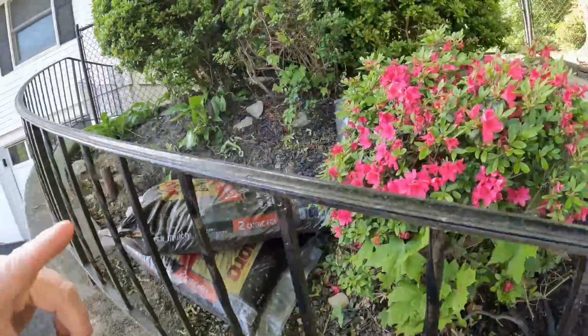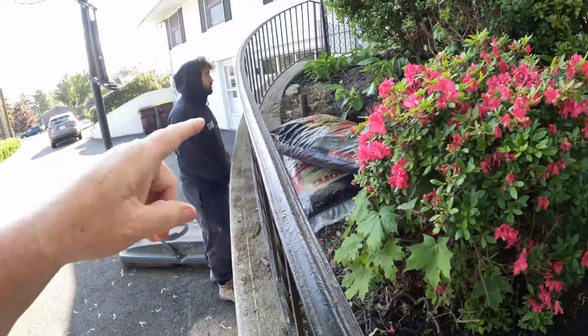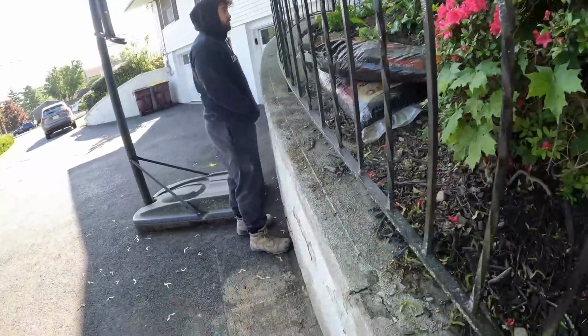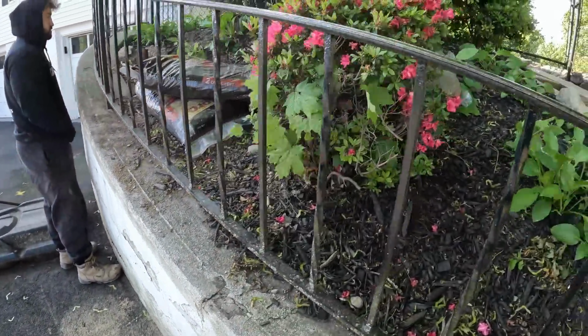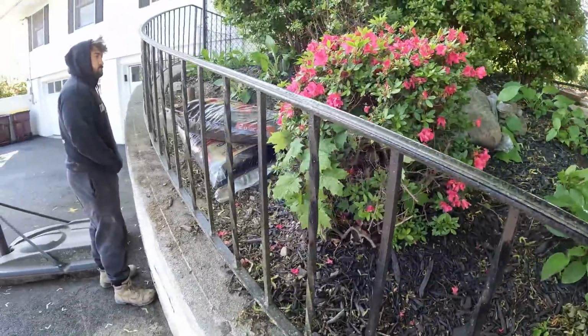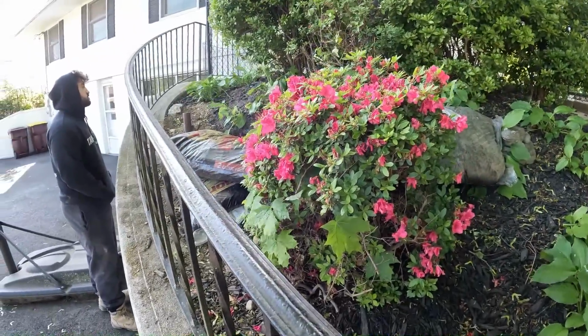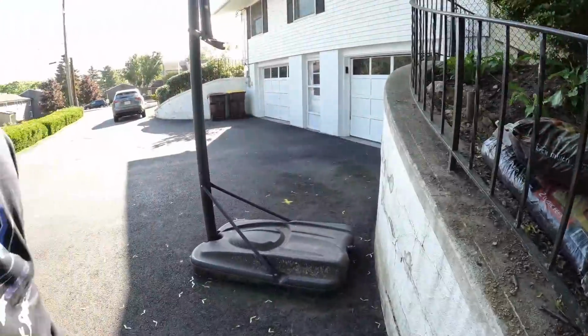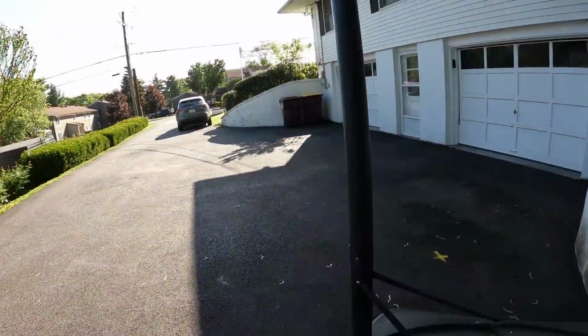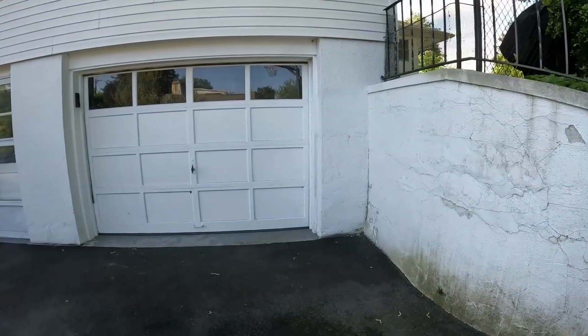We're going to dig all this nice foliage up. I'll sit right about here, see where that pipe goes. Hopefully no kind of metal dead men go in to support this wall. Dig this up, put it in the truck, and run an investigation. Get our metal detector down there, figure out that pipe. I'm going to go to those 2 return and suction lines, and like I said, I'm going to put some vacuum on it and see what I pull.